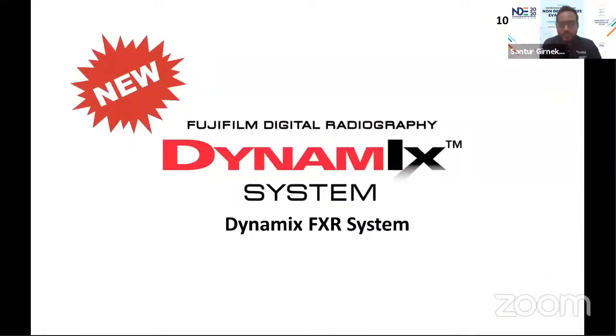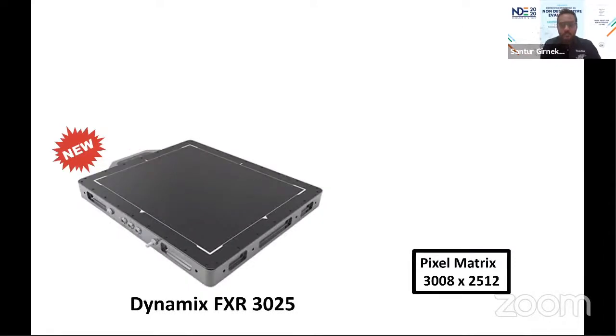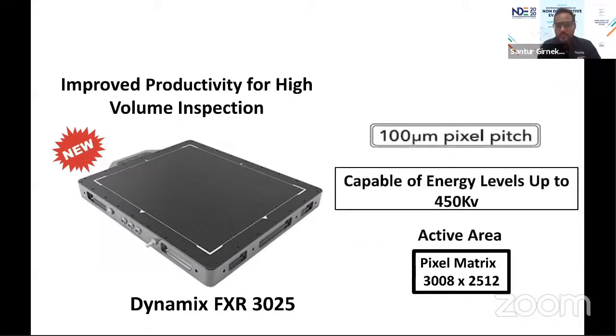Coming to the new product line which has been included, there are two Dynamics models: the Dynamix FXR 3025 and the Dynamix FXR 1621. If I'm talking about the Dynamix FXR 3025, the pixel matrix is around 3008, with improved productivity and high volume inspection. The pixel pitch is about 100 micron and it is capable of an energy level up to 450 kV. For applications like tube inspections and pipeline inspection, this would be a very good choice for real-time and online inspection.